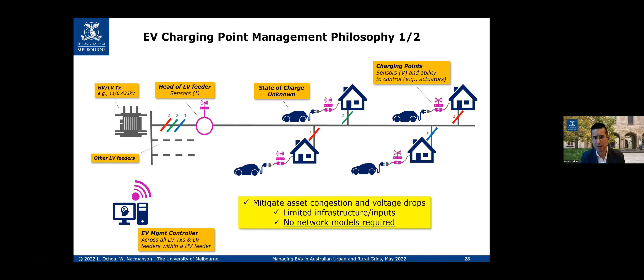We check the corresponding feeders in terms of voltages and conductors, and then we start disconnecting in a hierarchical way. The moment we see there's a problem, or we're close to one, we disconnect as many charging points as we consider adequate. Likewise, the moment we think there's no problem but there's headroom for capacity and voltages are okay, we estimate how many reconnections can happen from the queue of cars recently disconnected.